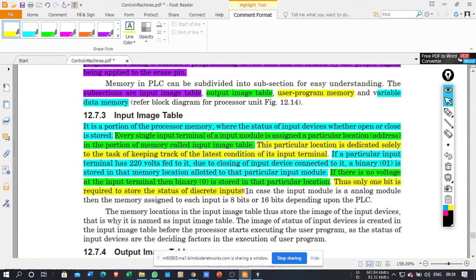In case the input module is analog, not all the inputs are digital. Some inputs may be analog, and if the input is analog, then we cannot use a single bit to store the status of that input. So in that case, I can use 8 bit or 16 bit, depending on the PLC, for storing the analog signal, because an analog signal does not have a discrete state. It will change with respect to time.